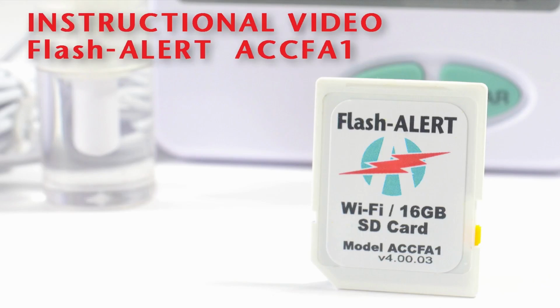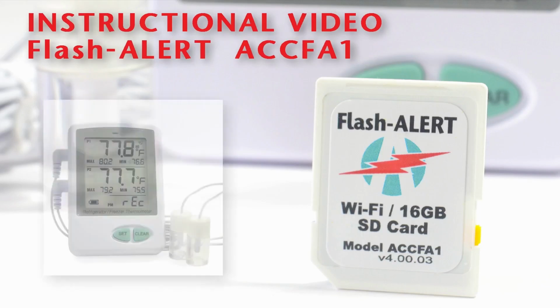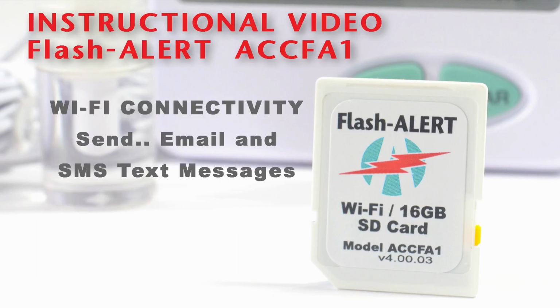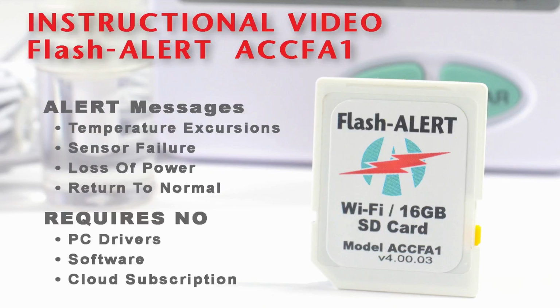In this instructional video, we will be covering the Flash Alert SD card that replaces the standard SD memory in the ACCRT8017 data logger. This upgrade card is not only memory, but includes a Wi-Fi radio that enables the data logger to send email and SMS text messages for temperature excursions, sensor failure, or loss of power, and alert messages to show if conditions have returned to normal.